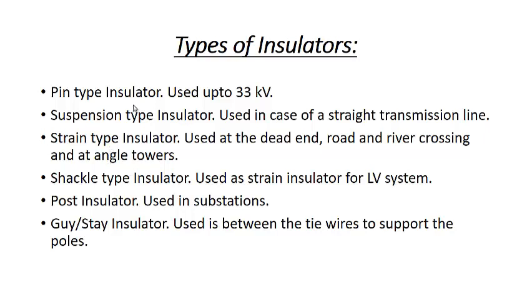It is used in angle towers when the transmission line is bent. It may be used in dead end, road or river crossing, etc. Wherever there is a strain or net force acting on the transmission line or towers, we use a strain type of insulators. They are actually identical. Only difference will be that their mechanical strength should be more as compared to suspension insulator because they have to bear the strain of the transmission line or tower.